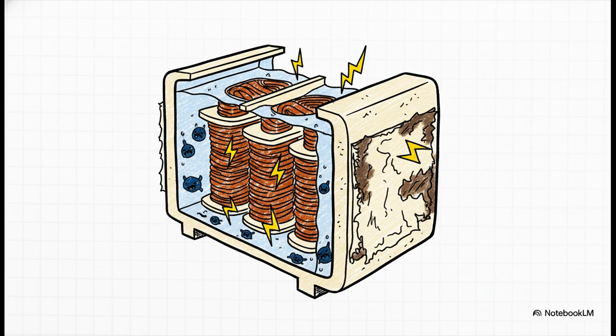It just wrecks the oil's dielectric strength. You can think of it like poking a bunch of holes in a raincoat. Suddenly, the oil can't do its job of insulating all those high-voltage parts. And what's worse, it starts to destroy the paper insulation wrapped around the windings. It is a total recipe for disaster.